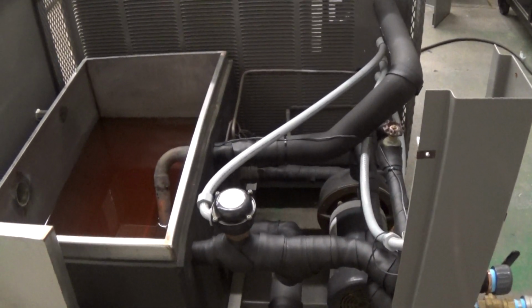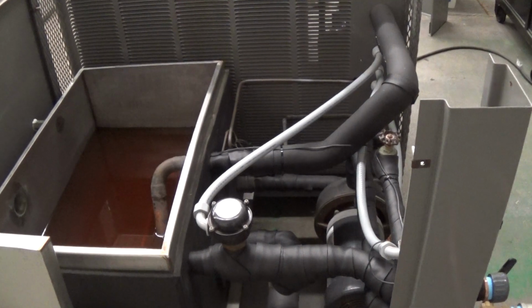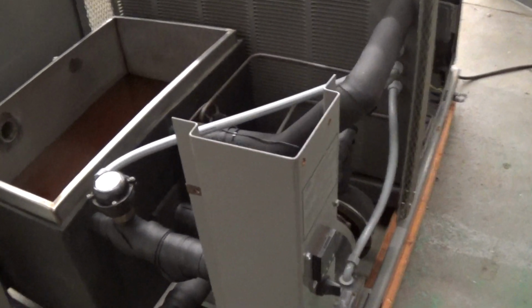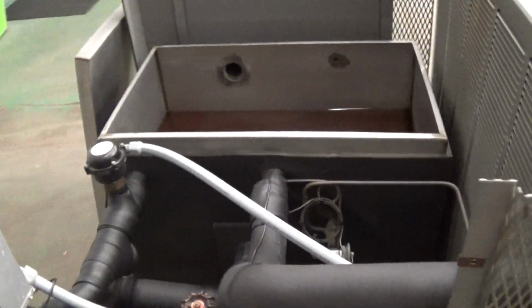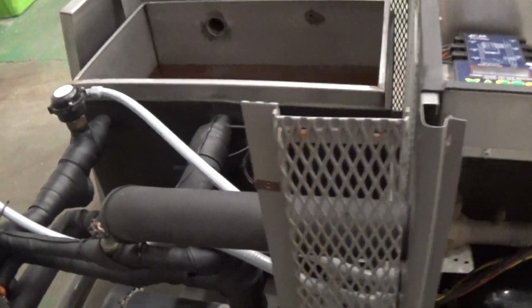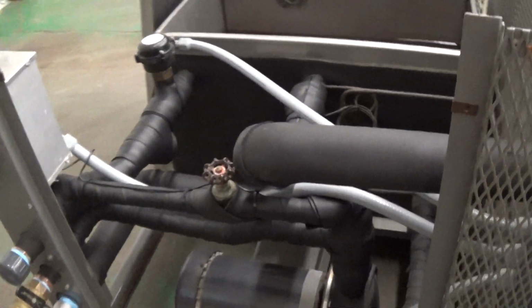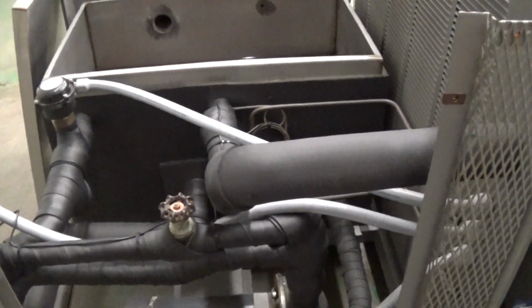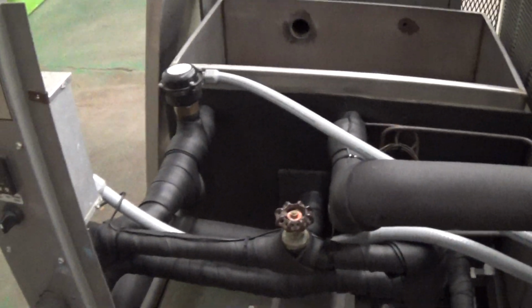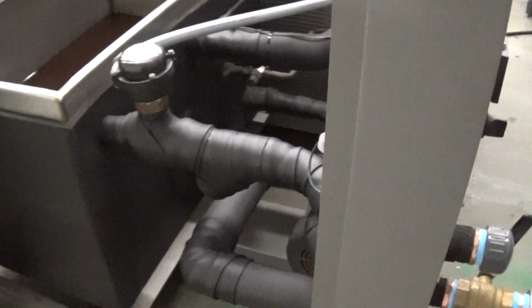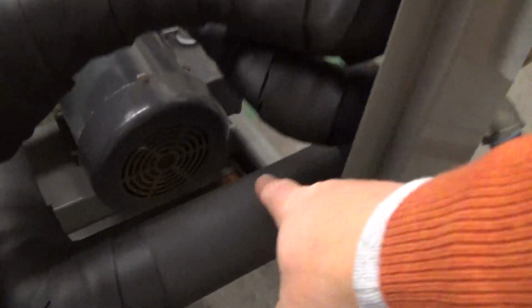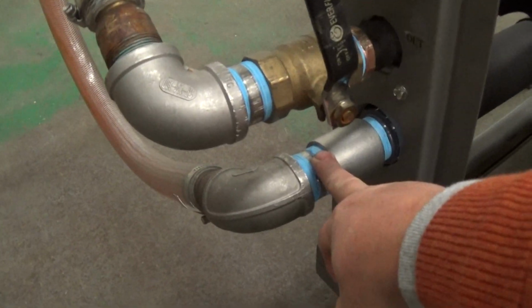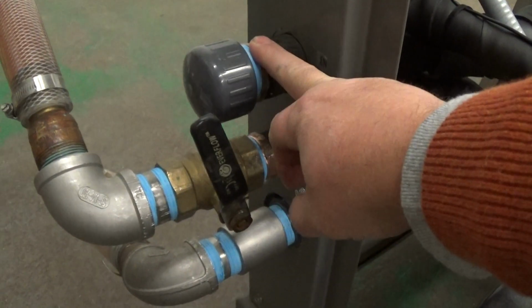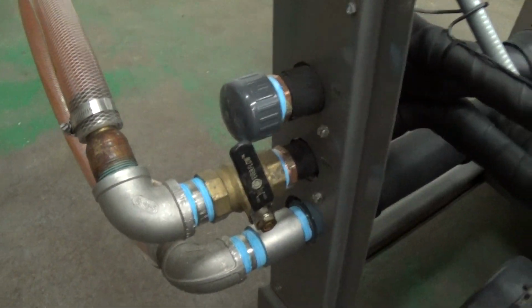One of the main things we do on a refurbished or used chiller for a glycol brewery application is we ensure that the piping is correct for the glycol loop. In this case, we had to modify that. So what that means is we put in a new return line, which is this line here, coming back to the tank, and that's what you can see set up right here. That's our new return line, and we actually had to cap the old return line. So what does all that mean?